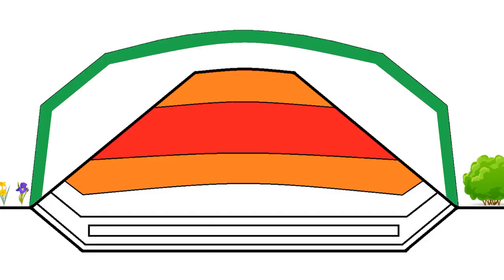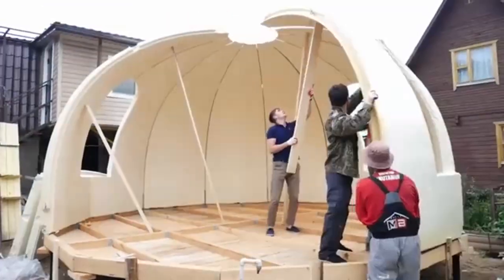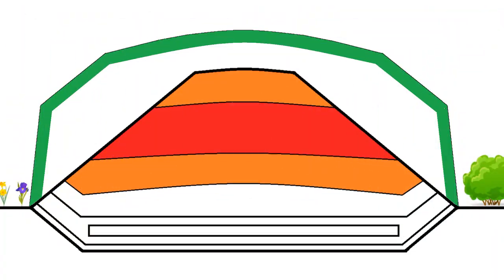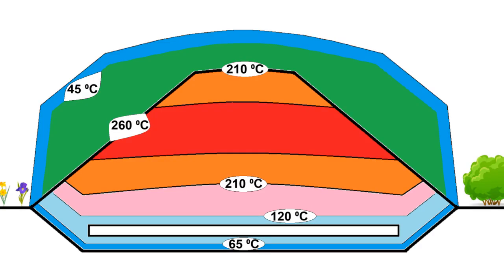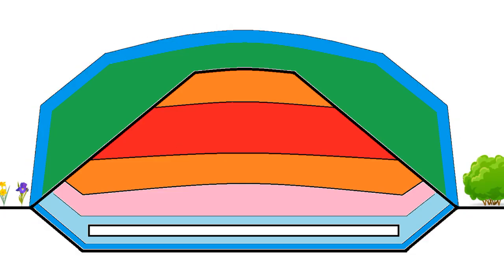Our cone is covered by a durable cap, possibly made from polystyrene foam sheets with a total thickness of 25 cm, consisting of several dozen modules glued together with polyurethane foam. The space is filled with cheap loose mineral wool or urea-formaldehyde foam, with total thermal insulation thickness ranging from 2 meters at the top to 1 meter at the edges. The maximum temperatures at the end of September confirm that the polystyrene remains below its maximum allowable temperature. Polymer layers must be installed to protect against moisture and rainwater penetration, and water vapor removal from the hot sand and insulation is an important challenge.